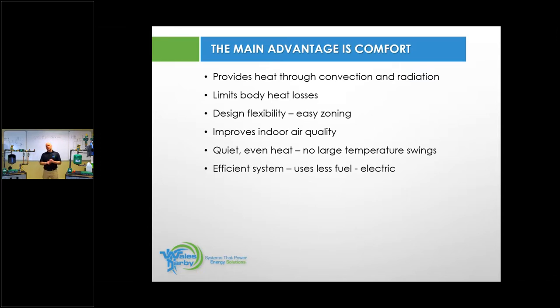And efficiency. With condensing boilers, obviously, we see guys out there advertising 95% efficient, and that's true at certain areas, and that's great. On the combustion side, we've gotten really efficient, so we use less fuel. But in addition to getting really efficient on the gas or oil side, we now also have the ability to be more efficient with these E-series circulators. These are DC-driven ECM circulators, up to 85% more electrically efficient than a typical AC circulator. So now we can really take a snapshot of the whole job and see what we can do to make it fuel smart and electric smart. So we'll go through that.